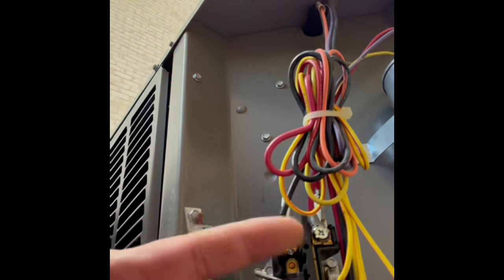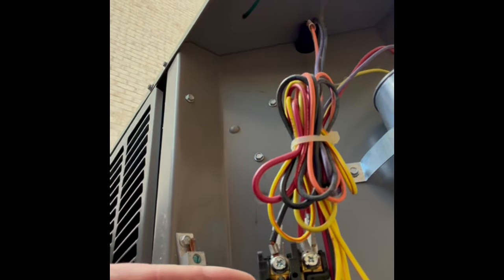So when your thermostat sends a call for cool, this guy plunges in, creating an arc. And if you look in there, you can see that this one is pitted. So this contactor would be deemed needing to be replaced. If not replaced, we run the risk of having this contactor ultimately weld itself shut to the point that the outdoor unit doesn't cut off.